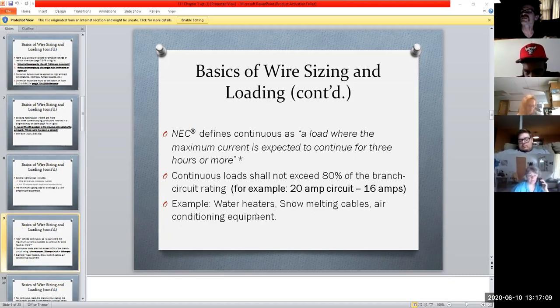Water heaters. If you had an electric water heater, it would have to be keeping the heat going constantly, so that thing is expected to run. Air conditioning equipment during the summer, those little motors kick off for the condenser and that kind of thing. If you get one of those nice driveways where you have the snow melting cables down in the center of it, those things will run for a really long time. And that's something where we would consider it what they call continuous duty. So it's running more than 3 hours at a time. That's a constant current delivery kind of thing.